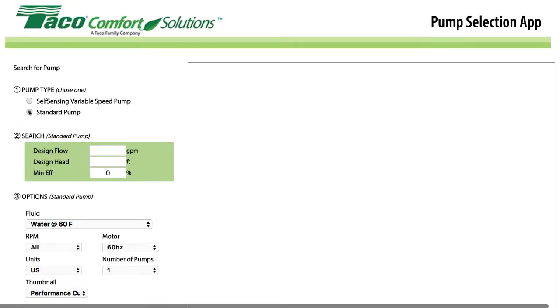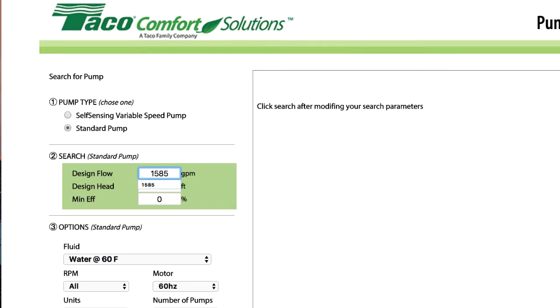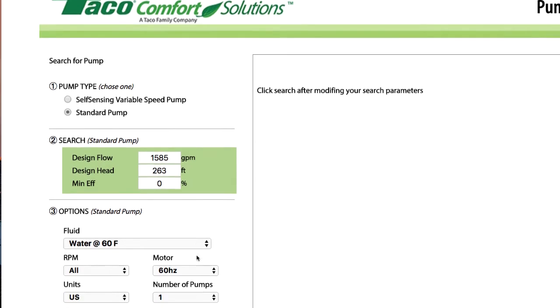We'd like to get a standard pump. Our design flow is 0.1 cubic meters per second, which we calculated to be 1,585 US gallons per minute — being a US company, they don't bother to mention they're US gallons. Our design head is 80.27 meters, which converts to about 263 feet, and we won't specify a minimum efficiency.